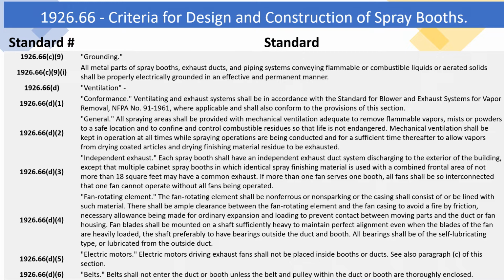1926.66(d) Ventilation. 1926.66(d)(1) Conformance. Ventilating and exhaust systems shall be in accordance with the standard for blower and exhaust systems for vapor removal, NFPA No. 91-1961, where applicable, and shall also conform to the provisions of this section. 1926.66(d)(2) General. All spraying areas shall be provided with mechanical ventilation adequate to remove flammable vapors, mists or powders to a safe location and to confine and control combustible residues so that life is not endangered. Mechanical ventilation shall be kept in operation at all times while spraying operations are being conducted and for a sufficient time thereafter to allow vapors from drying coated articles and drying finishing material residue to be exhausted.